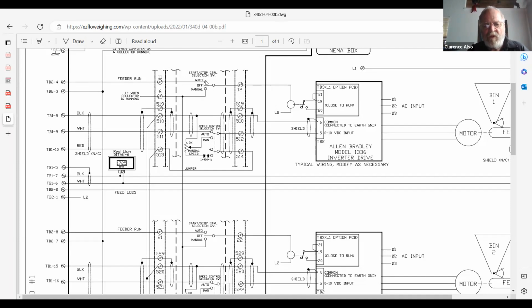And if you're in the automatic position, it will take off automatically, and it energizes this relay. You've got your L2 on one side, and if you put a hot on the other side, or if it's manual, you've got a hot the other time, it'll energize. This is a relay, and that relay set of contacts is then going to close something between terminal 19 and 20.